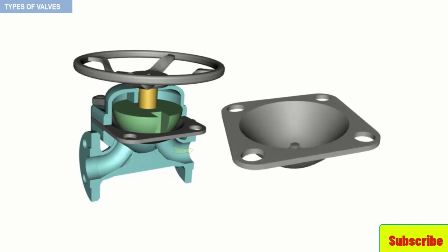Here you can see an enlarged view of the diaphragm in the closed position of the valve. The maximum pressure the valve can be subjected to is a function of the diaphragm material and service temperature. Also, the system hydrostatic test pressure must not exceed the maximum pressure rating of the diaphragm.